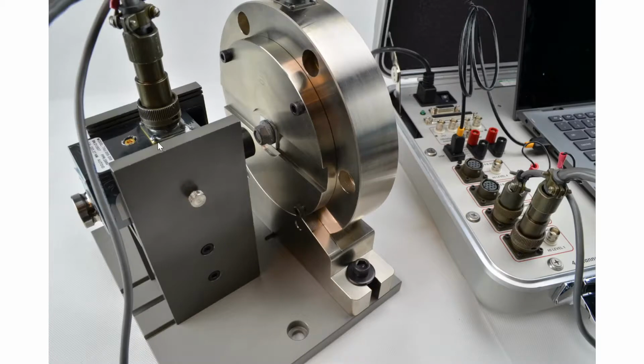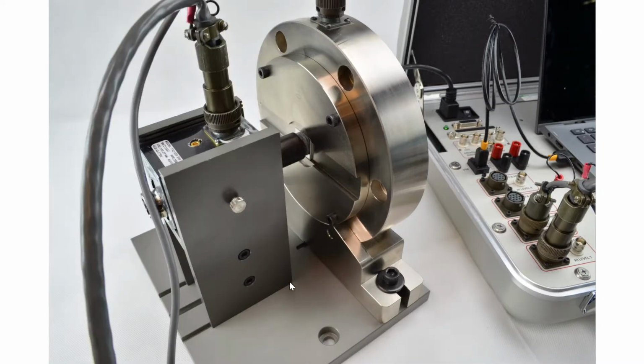Also, we are installing the torque angle transducer in this area, so it holds it nice and tight. Then we engage the torque angle transducer with the socket with the bolt. They're all now connected through the cables to the MC950. This is torque and angle, which corresponds to this unit, and load cell, which corresponds to this unit. Now they're all engaged together, and they're ready to go.